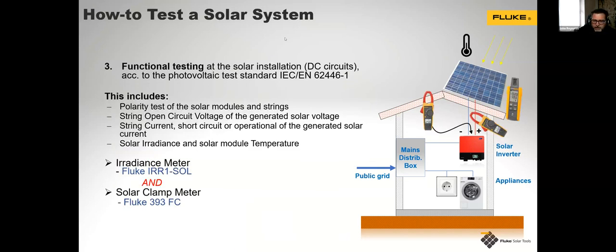Moving on to functional testing, and we can see that the graphic has changed there. We're going to be needing to look for the polarity of the solar modules and strings, open circuit voltage of the generated solar voltage, string current, short circuit or operational of the generated solar current, and also look at the solar irradiance and solar module temperature. We'll be going into that slightly later on. To do that for the irradiance, use a Fluke IRR1 meter, and for the clamp meter, which theoretically should be the go-to for both maintenance and installers of solar, the solar clamp meter Fluke 393 FC.